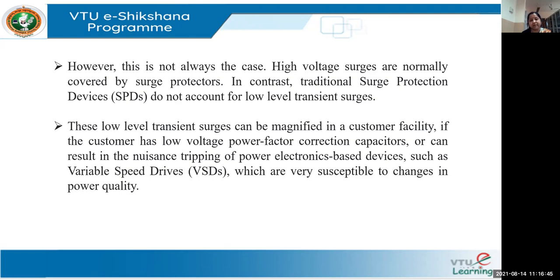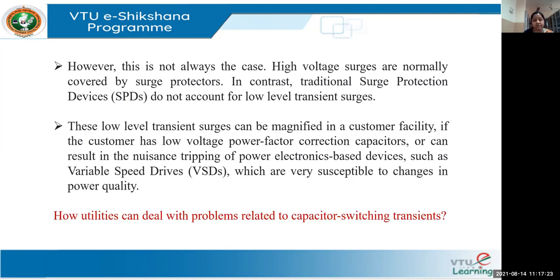These low-level surges can be magnified at the customer end or at the utility end. In the customer facility, if the customer has low-voltage power factor correction capacitors, it can result in unwanted tripping of power electronic devices such as VSDs, which are very susceptible to changes in power quality. We need to ensure that unwanted tripping does not happen in the system due to these surges.